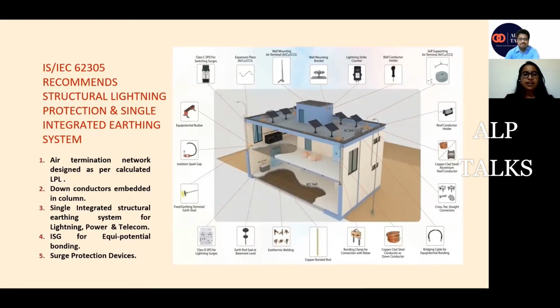The prevailing standard for lightning protection systems is IEC 62305. Initially, it was IS 2309, but IS 2309 has now been superseded by IEC 62305, and our Indian standards have also adopted the very same IEC standard. So it is now IEC 62305, which is the globally accepted standard. It tells us how we can do the risk assessment calculation, and after that, how we will install the lightning protection system at different levels to protect our building.